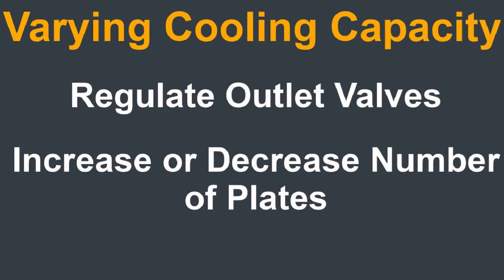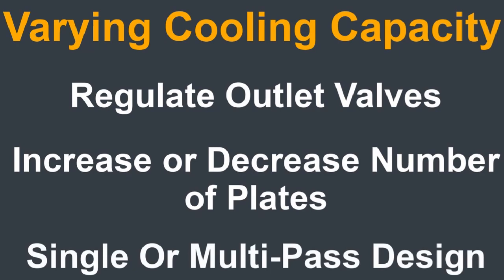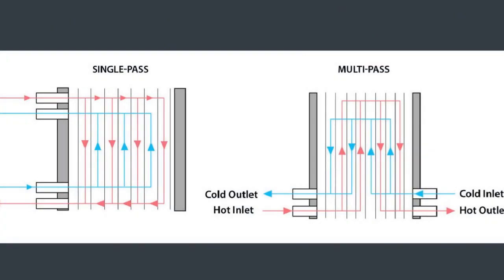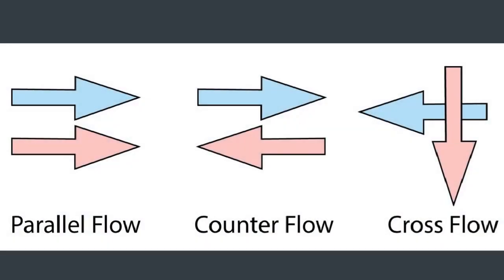The final method of varying a plate heat exchanger's cooling capacity is to use a single-pass or multi-pass design. Single-pass heat exchangers allow the 2 flowing mediums to flow past each other only once. Multi-pass heat exchangers allow the flowing mediums to flow past each other several times. Most plate heat exchangers use a single-pass design. Flow through a plate heat exchanger may be parallel, cross or counter. Plate heat exchangers usually use counter flow, as this is the most efficient type of flow for heat transfer. Counterflow is also sometimes known as contraflow.